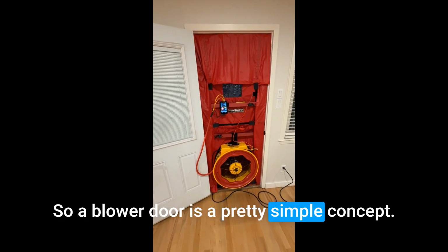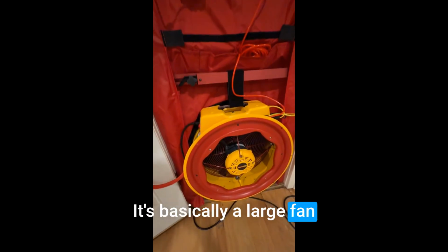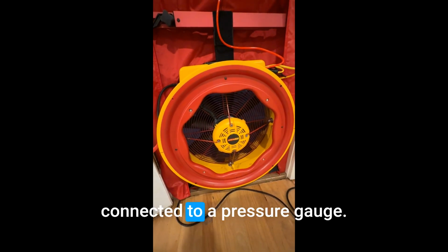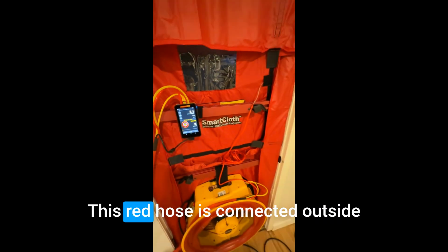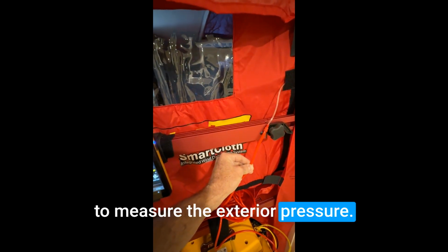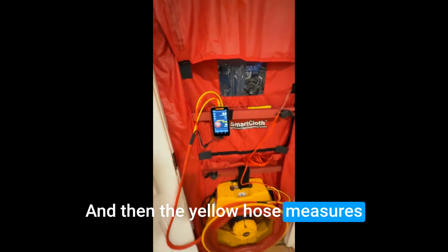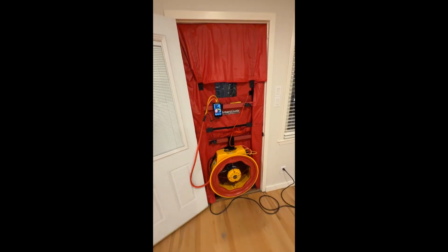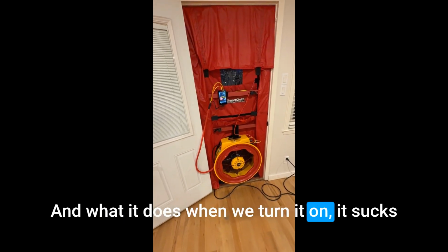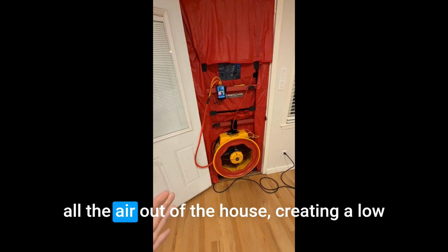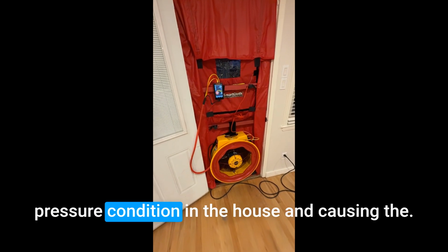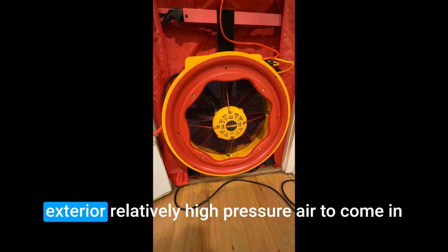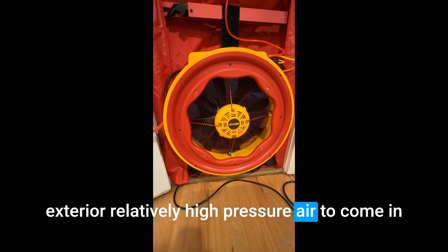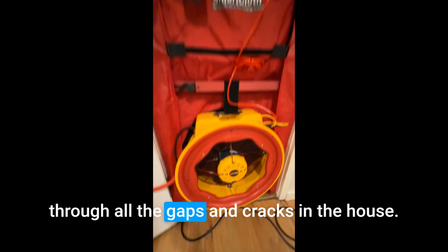So a blower door is a pretty simple concept. It's basically a large fan connected to a pressure gauge. This red hose is connected outside to measure the exterior pressure, and then the yellow hose measures the pressure inside the house. And what it does when we turn it on, it sucks all the air out of the house, creating a low pressure condition in the house and causing the exterior relatively high pressure air to come in through all the gaps and cracks in the house.